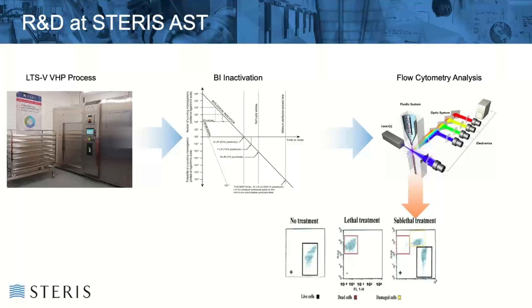Regarding technology development, it starts behind the scenes. When we look to develop a new technology and solutions, there's often extensive development activity. This slide shows a little of what we've been doing over the last few years around VHP. Being part of a large and diverse service organization allowed us to tap into the scientific knowledge within the wider STERIS community and develop solutions for our customers. We've leveraged the expertise of our healthcare division in VHP and worked at industrial scale to investigate microbiocidal inactivation, using the latest microbiology techniques, focusing on gaining the deepest understanding of the process to design the most efficient process best suited to the needs of the medical device product.